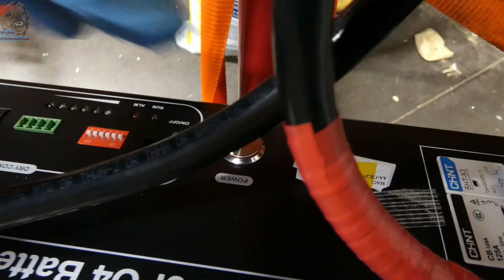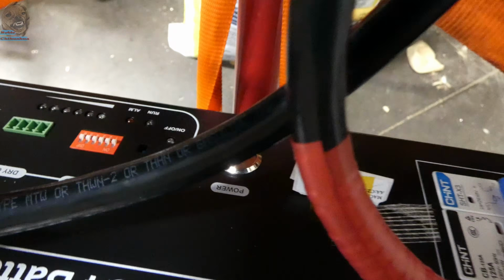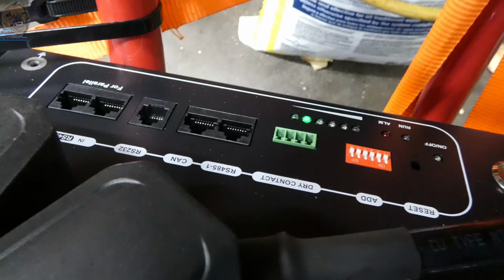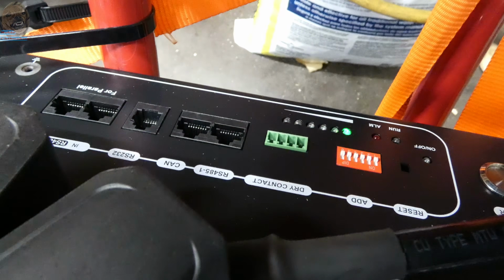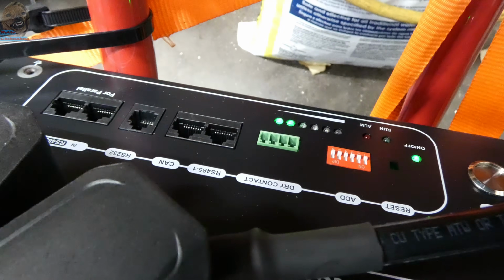Once everything was wired up, I did a basic function test. I powered it on: battery breaker first, then the round BMS button on the battery, then the black switch on the inverter. It took a few seconds and the inverter powered up cleanly.